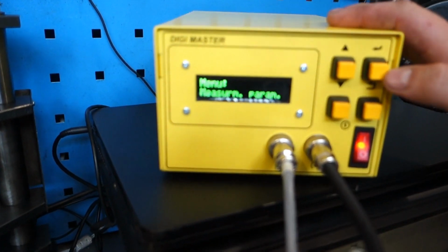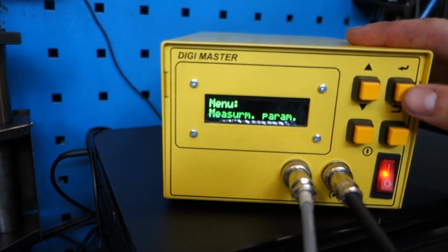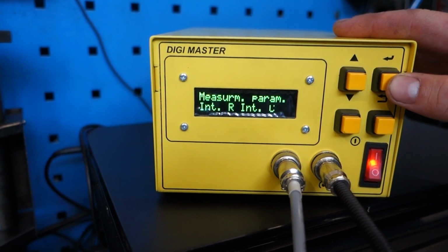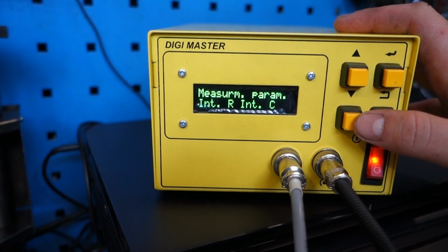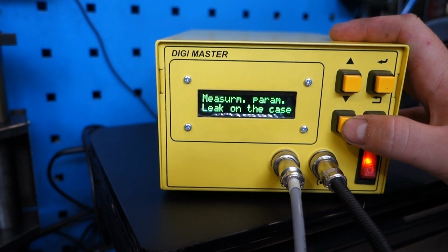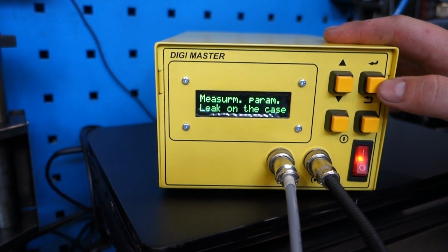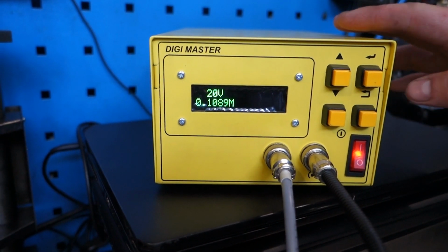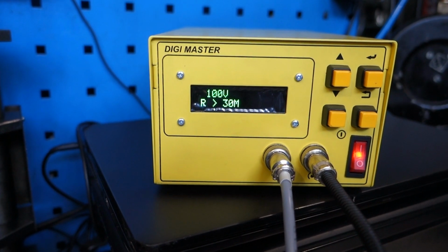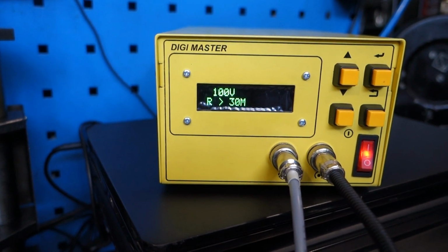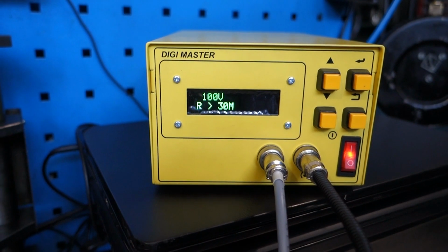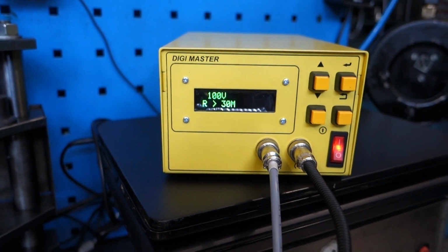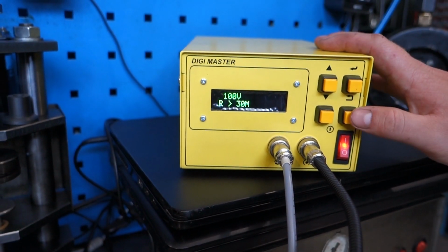We move to measurement parameters, we press OK, then we move down to leak on the case, we press OK. The answer is 30, perfect. If the answer is 10, it's perfect. If the answer is 1, then you can throw away the injector, there's leakage on the case. Alright.